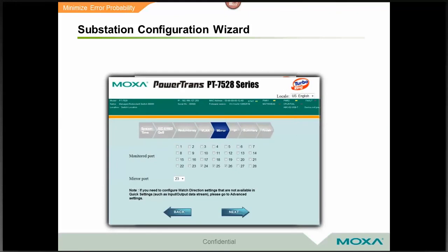Mirror ports are a way of saying: on ports 24, 25, and 26, I want all the data going in and out of those ports sent to port 23, so I can use that for historian or data logging, making sure I have all the data recorded somewhere for analysis in case something goes wrong. That's also a requirement for 61850, and best practice.